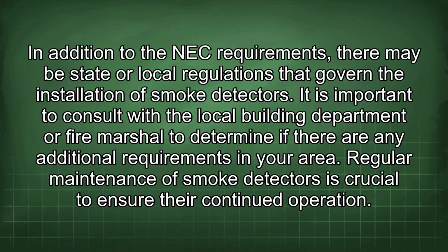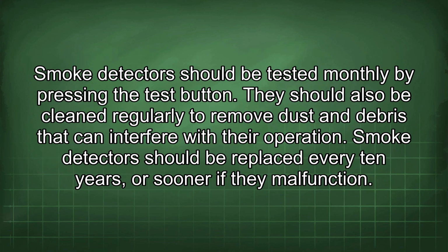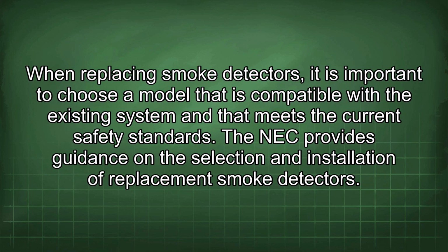In addition to the NEC requirements, there may be state or local regulations that govern the installation of smoke detectors. It is important to consult with the local building department or fire marshal to determine if there are any additional requirements in your area. Regular maintenance of smoke detectors is crucial to ensure their continued operation. Smoke detectors should be tested monthly by pressing the test button. They should also be cleaned regularly to remove dust and debris that can interfere with their operation. Smoke detectors should be replaced every 10 years or sooner if they malfunction. When replacing smoke detectors, it is important to choose a model that is compatible with the existing system and that meets the current safety standards. The NEC provides guidance on the selection and installation of replacement smoke detectors.